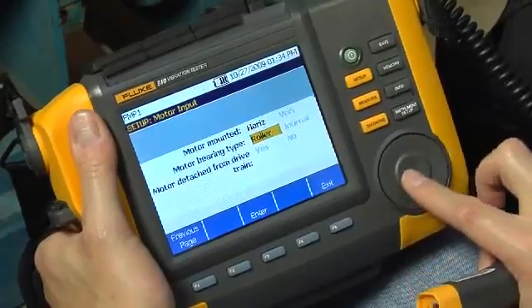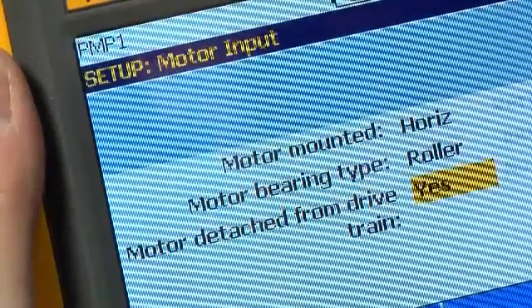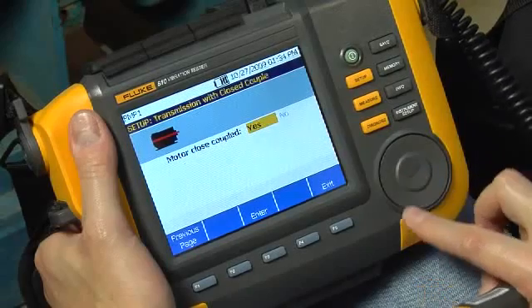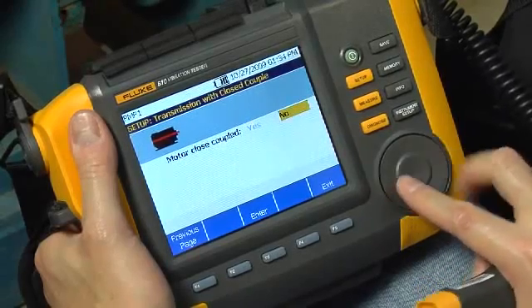Select Roller for motor bearing type, and select No for motor detached from the drive train. If you're only testing the motor and there is nothing attached to it, select Yes. Select No for motor closed coupled, and Yes for coupling between motor and next component.